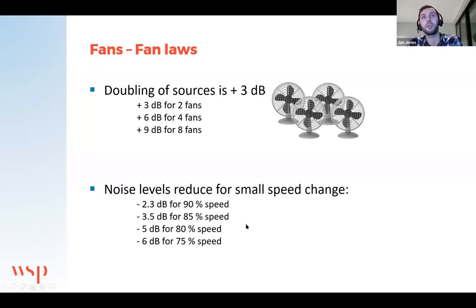This is an empirical formula which can be used to an extent, which predicts the reduction in noise level as a reduction of fan speed. You can see that for perhaps small decreases in speed, you can get a reasonable noise reduction. There is some solid theory there, and that is what happens. But generally, it's best assured by accurate noise data being received for equipment at the specified or required duty, such that it can be accounted for correctly.